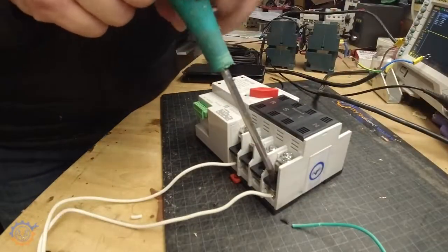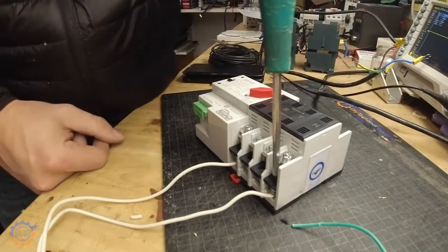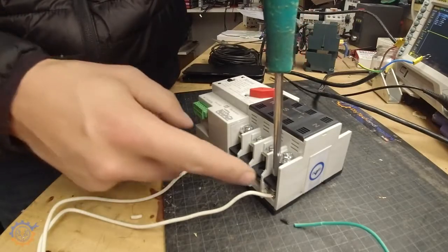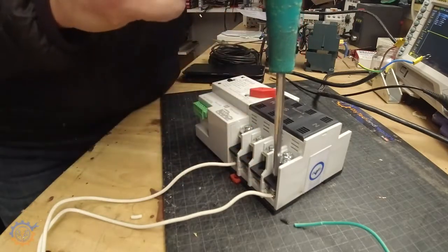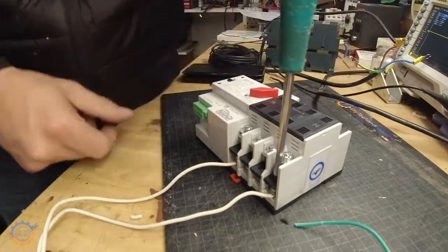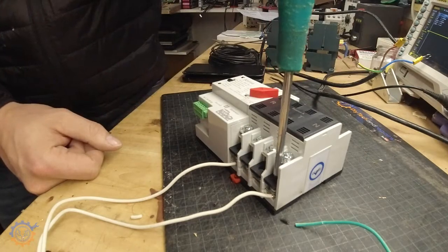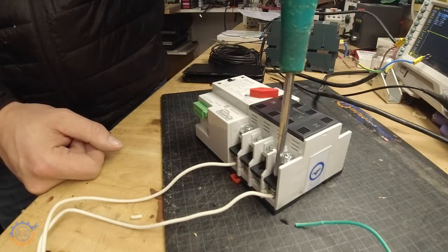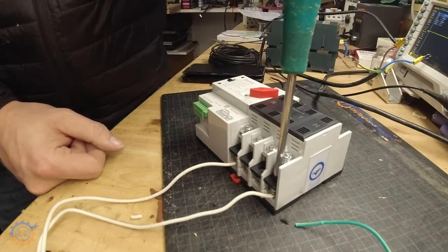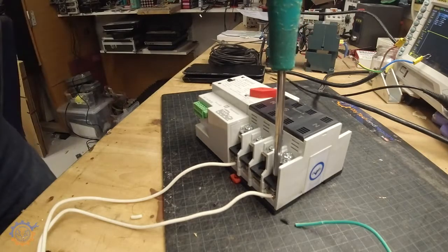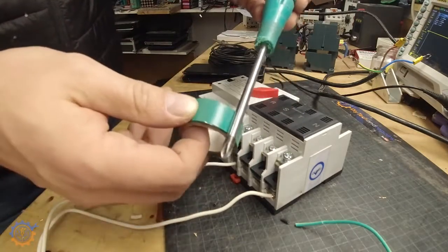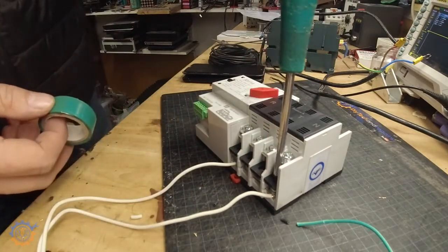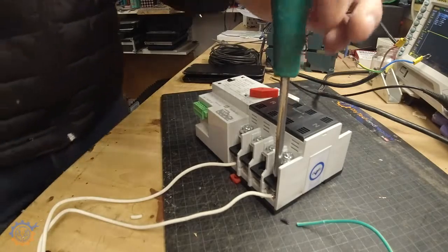When you are screwing the bottom side here, the screwdriver will touch the upper here. So if you haven't disconnected everything you easily can short this out. So if you're going to screw it like that, make sure you add some tape around the screwdriver so you don't mistakenly short this out.